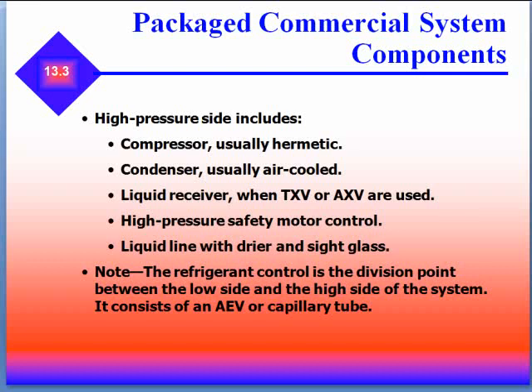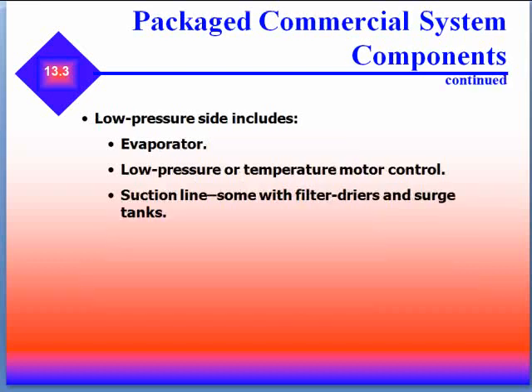The refrigerant control is the division point between the low and high side of the system, and it consists of an AXV or cap tube device. In a packaged commercial system, the low pressure side includes the evaporator, low pressure or temperature motor control, suction lines, some with filter dryers and surge tanks.